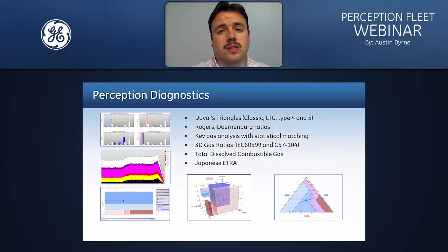Perception Fleet also still contains its inbuilt diagnostics. It has a suite of diagnostic tools built right into the application, ranging from Duval's triangles, classic LTC type 4 and type 5, Rogers, Doernenburg ratios, key gas analysis with statistical matching, 3D gas ratios using IEC 60599 and IEEE C57104, a total dissolved combustible gas chart, and Japanese ETRA. So they're all built right into Perception.